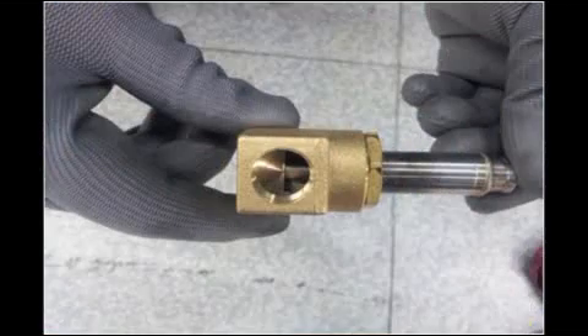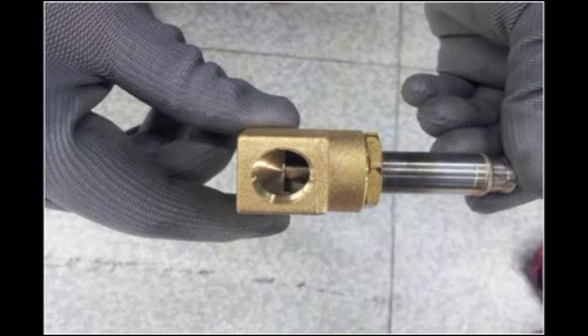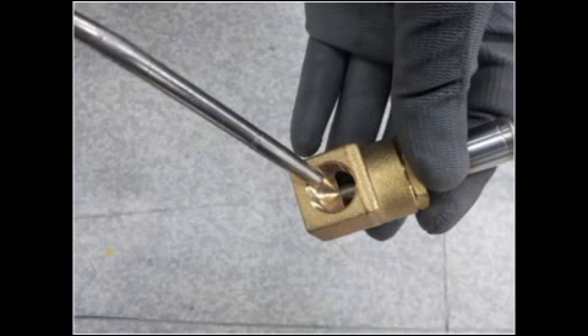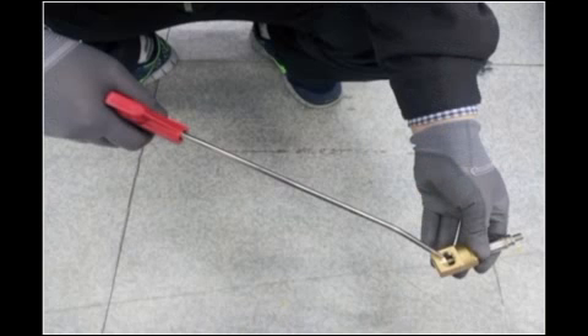Step 7. Disassemble the inner pipe of solenoid valve. Step 8. Immerse the valve in hot water, over 60, for 3 minutes and clean inside of the valve with compressed air, 4 to 7 kilograms per centimeter 2. Step 9. Reassemble the valve, following instructions in reverse order from Step 6 to Step 1.